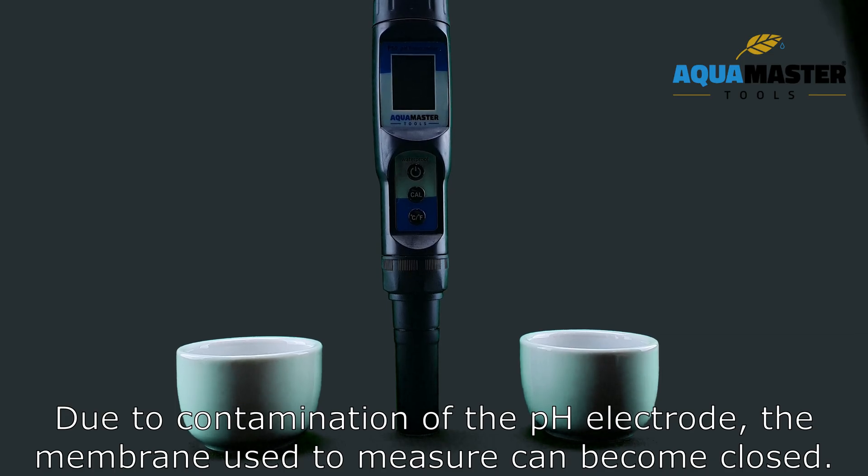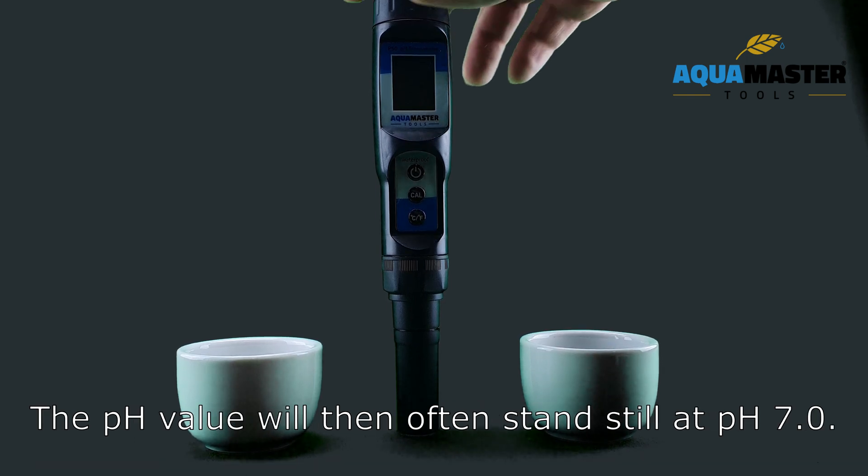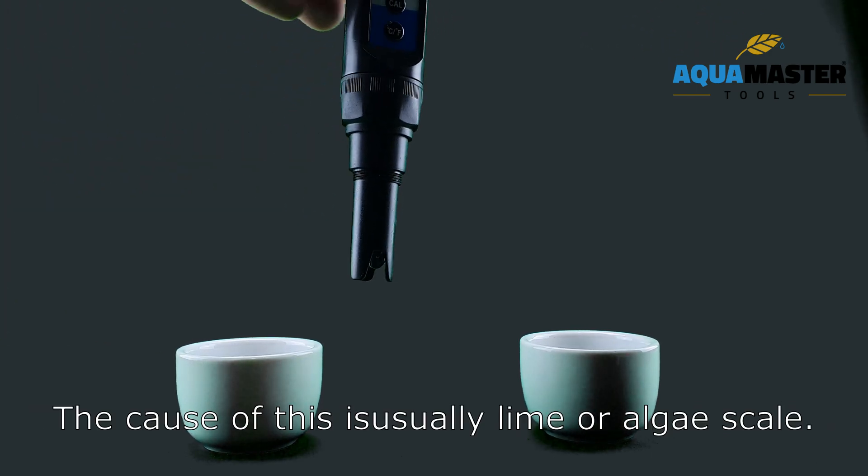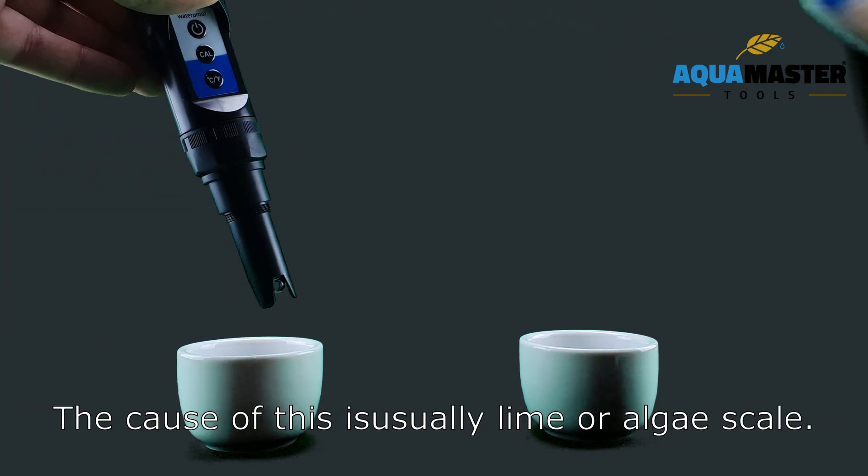Due to contamination of the pH electrode, the membrane used to measure can become closed. The pH value will then often stand still at pH 7.0. The cause of this is usually lime or algae scale.